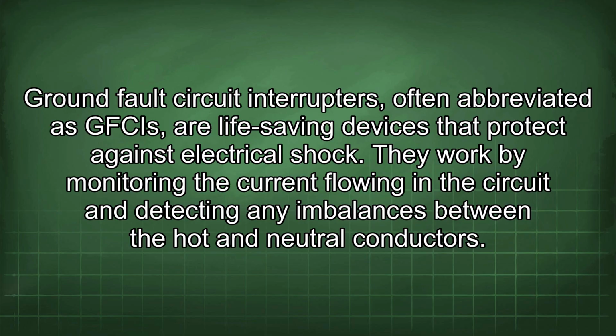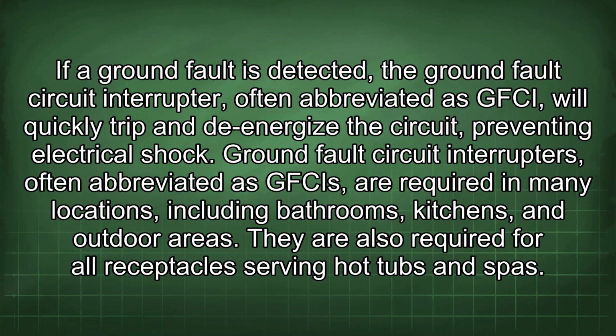Ground fault circuit interrupters, or GFCIs, are life-saving devices that protect against electrical shock. They work by monitoring the current flowing in the circuit and detecting any imbalances between the hot and neutral conductors. If a ground fault is detected, the GFCI will quickly trip and de-energize the circuit, preventing electrical shock. GFCIs are required in many locations, including bathrooms, kitchens, and outdoor areas. They are also required for all receptacles serving hot tubs and spas.